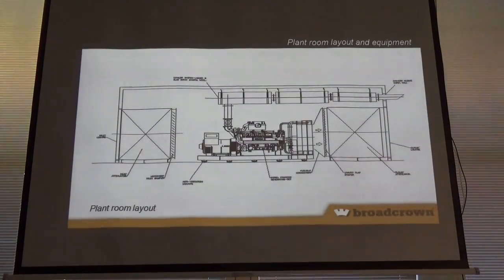Okay, so ducted discharge, but you can have multiple air inlet paths, as long as ideally you're delivering it to the alternator end to have a nice, clear, relatively laminar flow across the unit itself, to avoid hot spots on your exchanger, any problems with the alternator, etc. So you can put an attenuator there, which delivers air into the room nicely and draws it across. That fan performance and airflow is based on 250 pascals external resistance. You can easily lose 50 pascals for the inlet and maybe the discharge.